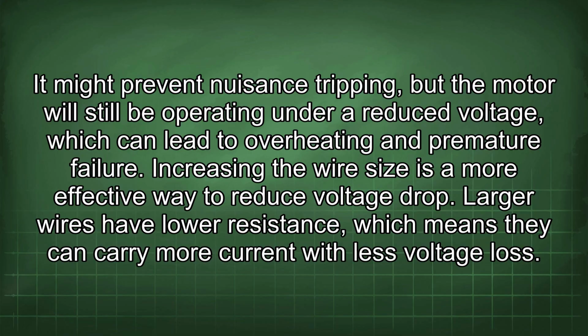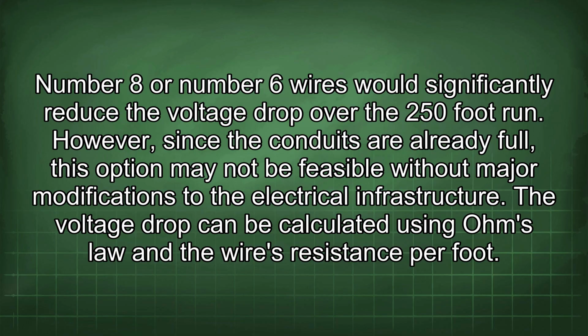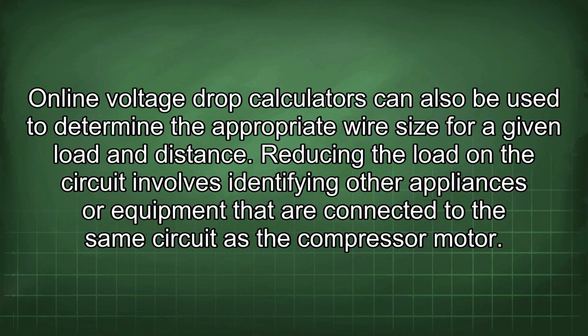Larger wires have lower resistance, which means they can carry more current with less voltage loss. Number 8 or number 6 wires would significantly reduce the voltage drop over the 250-foot run. However, since the conduits are already full, this option may not be feasible without major modifications to the electrical infrastructure. The voltage drop can be calculated using Ohm's law and the wire's resistance per foot. Online voltage drop calculators can also be used to determine the appropriate wire size for given load and distance.